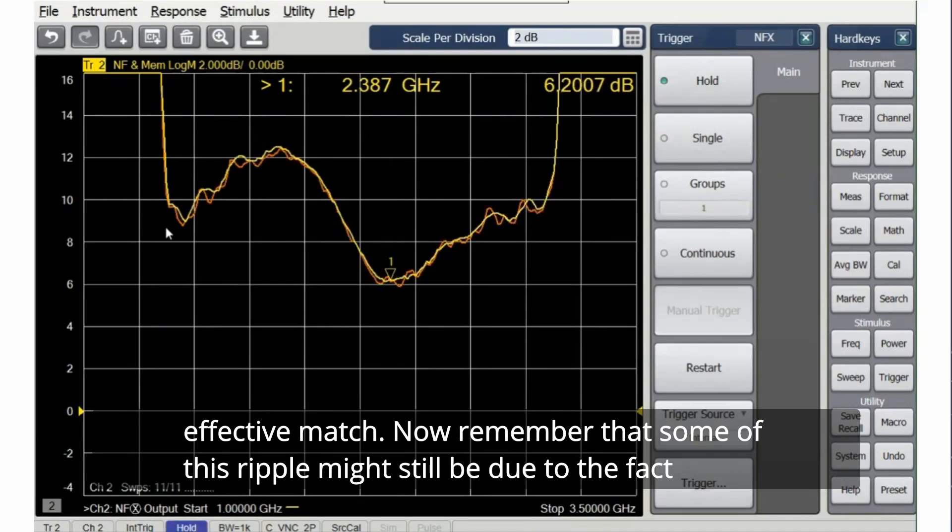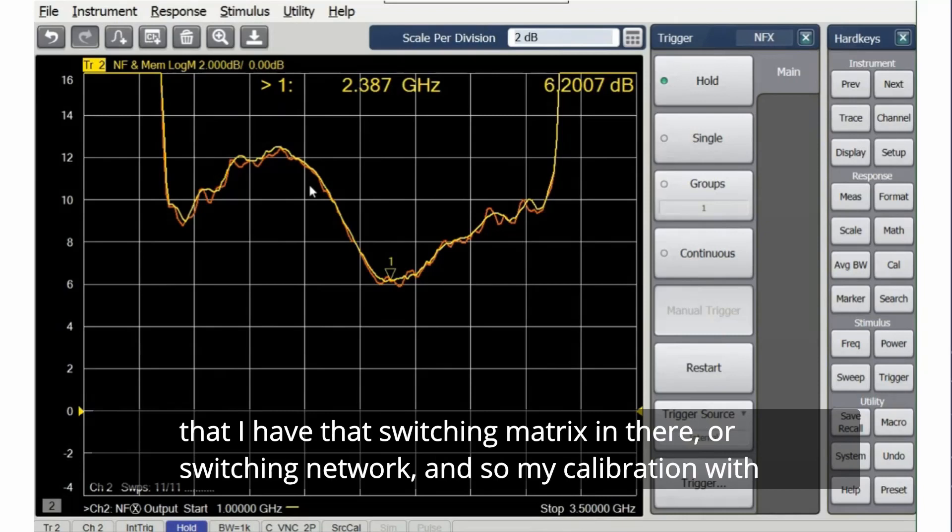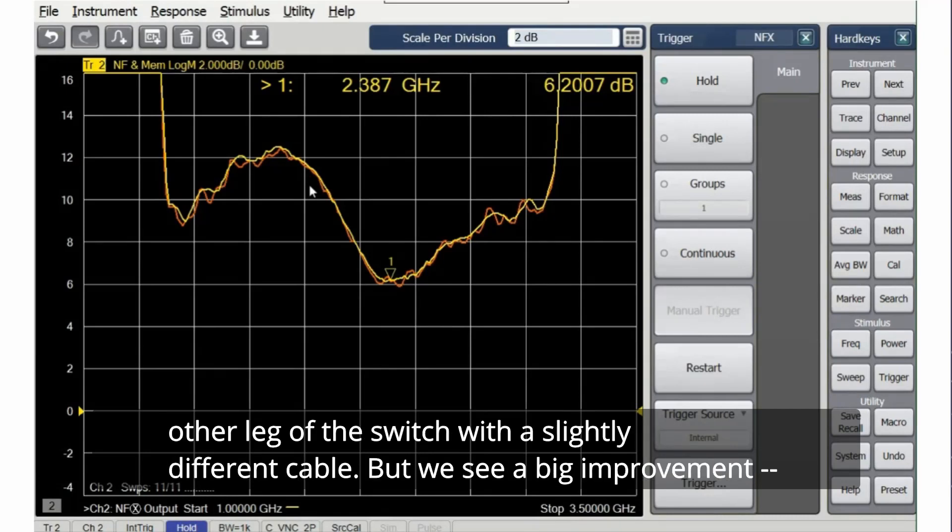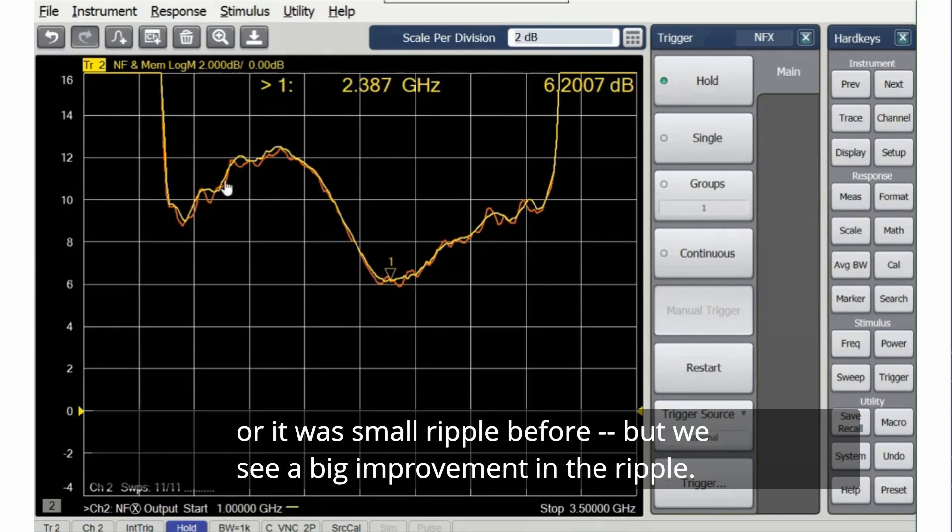Now, remember that some of this ripple might still be due to the fact that I have that switching matrix in there or switching network. And so my calibration with the e-cal is not really perfect compared to the input port of the converter because it is on the other leg of the switch with a slightly different cable. But we see a big improvement in the ripple.